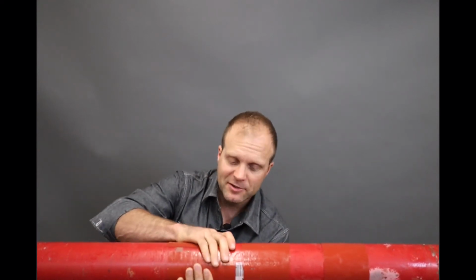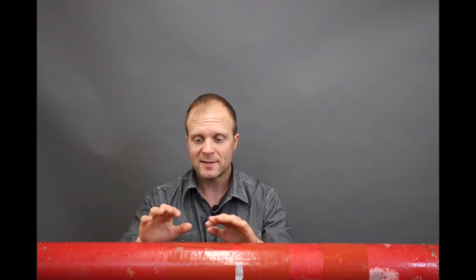And this actually has dual functions. It helps the sound from the flow meter get into the pipe and out for the sending and receiving transducers, but it also is used to attenuate the sound that's going through the pipe that we don't want. So what we want is the sound that's passing between the transducers and going through the fluid. What we don't really care about is the sound that's going around the pipe in its wall, in the wall thickness of the pipe. So this helps attenuate that so it doesn't corrupt our actual flow measurement or energy loss measurement. So it's that easy.